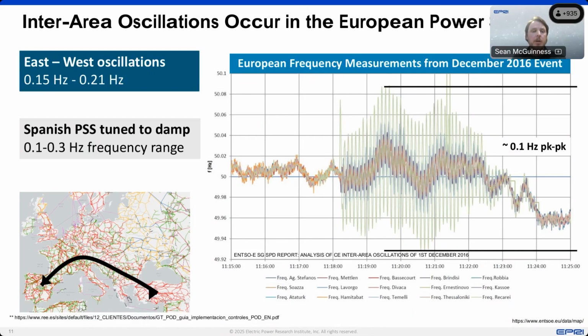As a result of that, we see that they took active measures in Spain to compensate for that. Their power system stabilizers are tuned to damp out that frequency range, in that 0.1 to 0.3 range. There are also oscillations around 0.6 hertz, which are also damped. This chart shows a pretty significant inter-area oscillation which occurred in 2016. So it is 9 years ago, but it's still relevant.